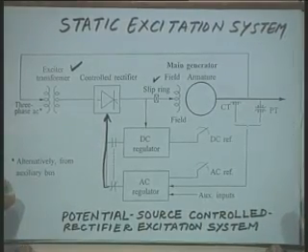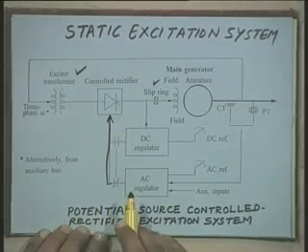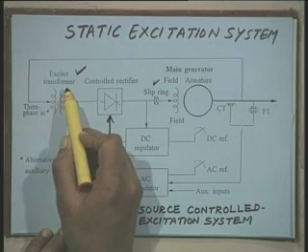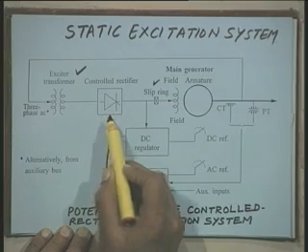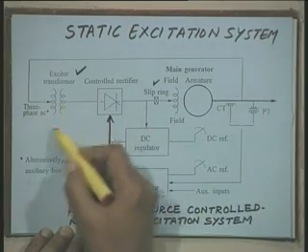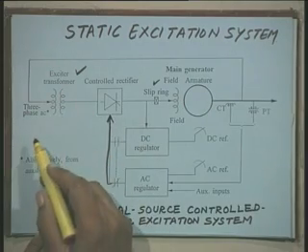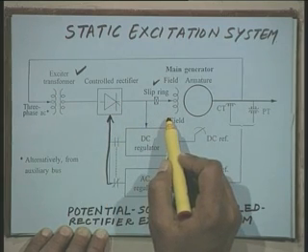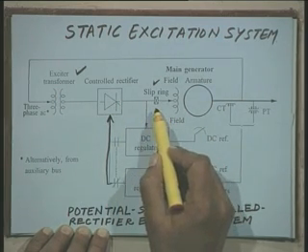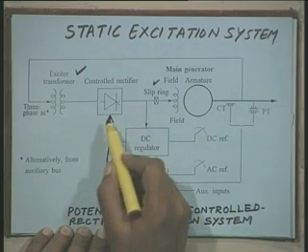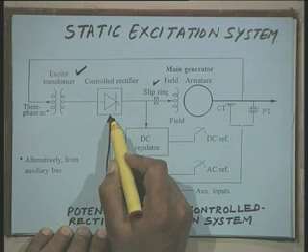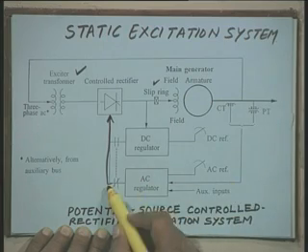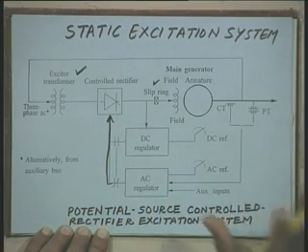The last excitation system model which we will talk about is the static excitation system model. Here I will discuss the excitation system model with an exciter transformer. We have a controlled rectifier; the excitation system power is derived through an exciter transformer, a 3-phase transformer, and the output is rectified using a controlled rectifier and fed to the field winding of the synchronous machine through slip rings. Our regulator acts on the controlled rectifier, that is, the AC regulator, which gets input from the current transformer and potential transformer. This will directly act on the controlled rectifier. This is a very simple excitation system model.